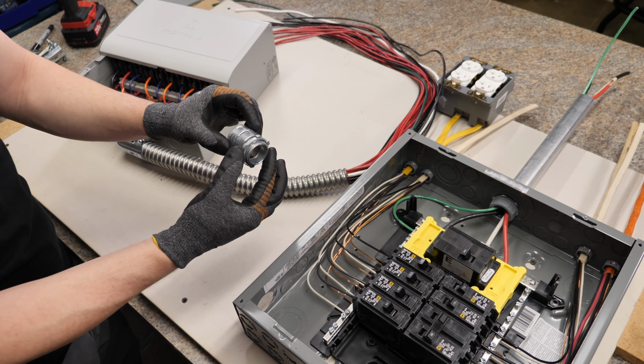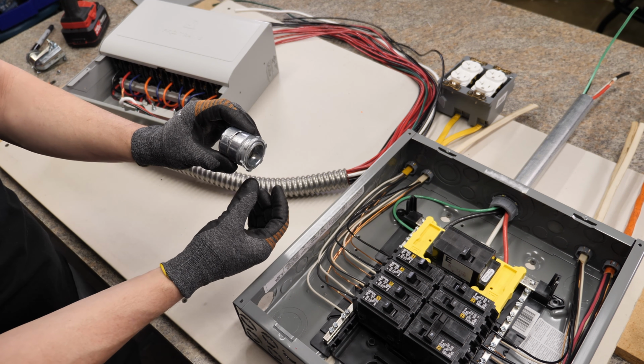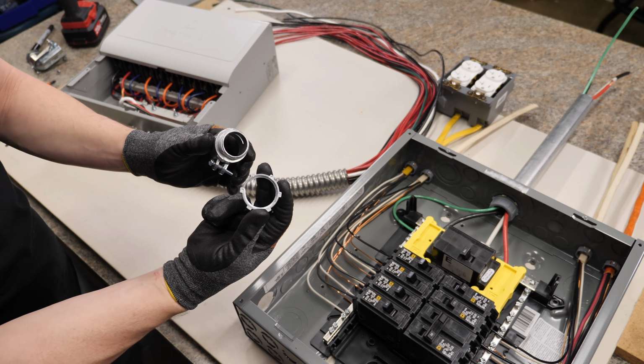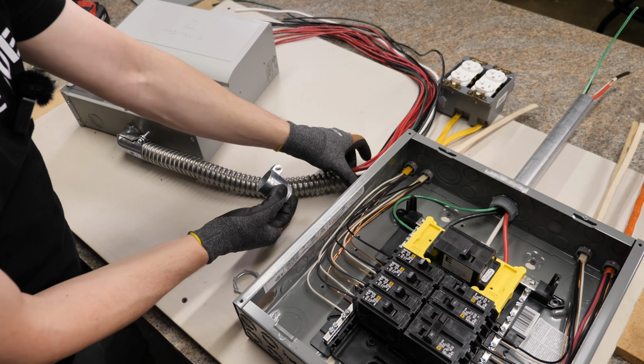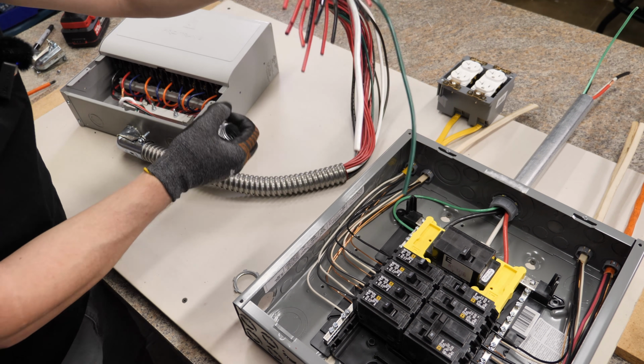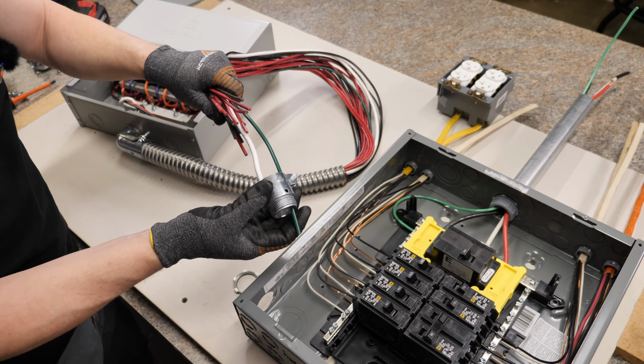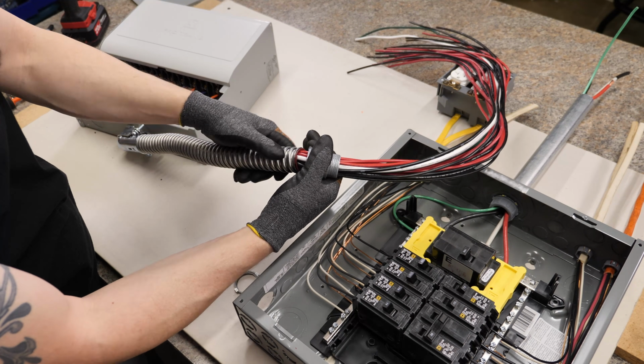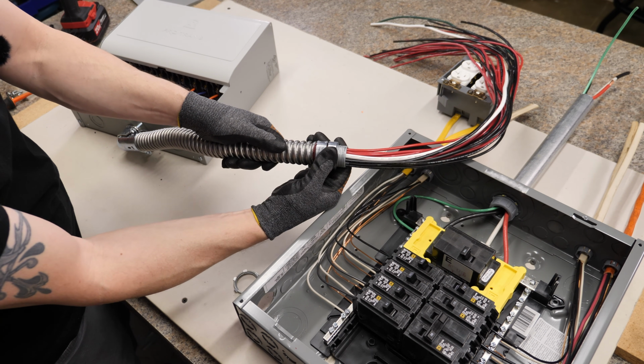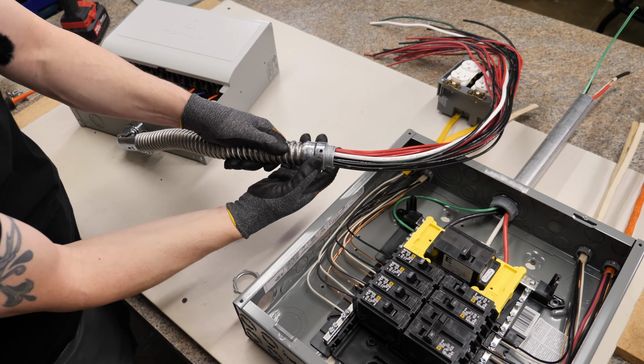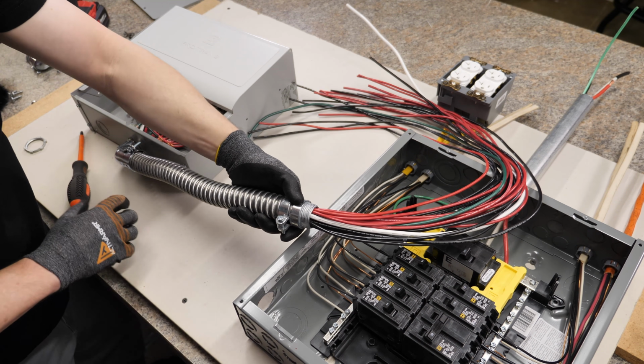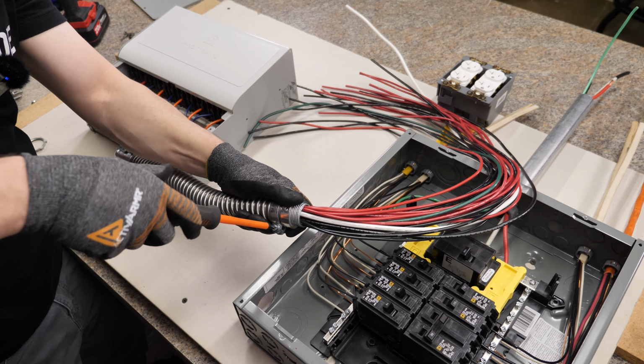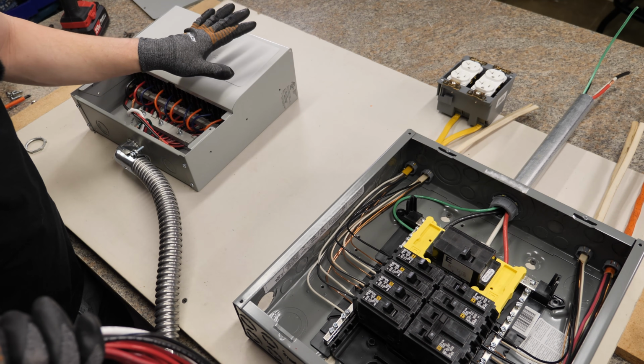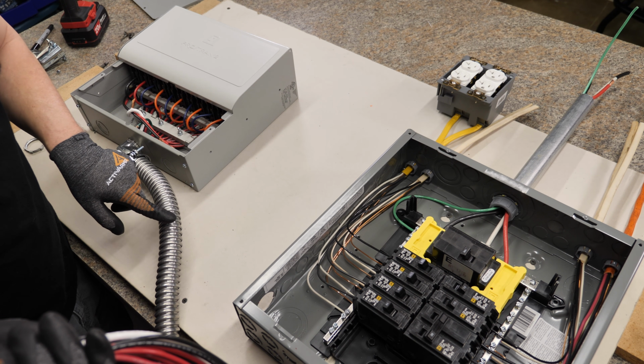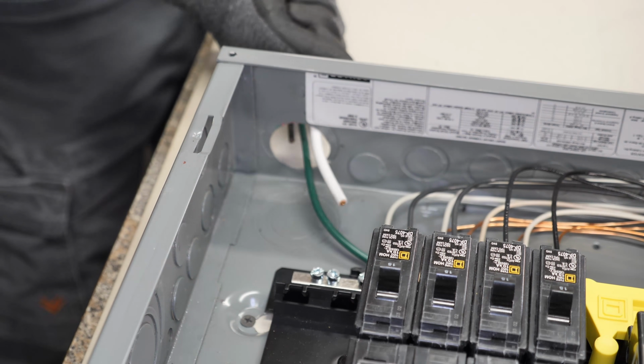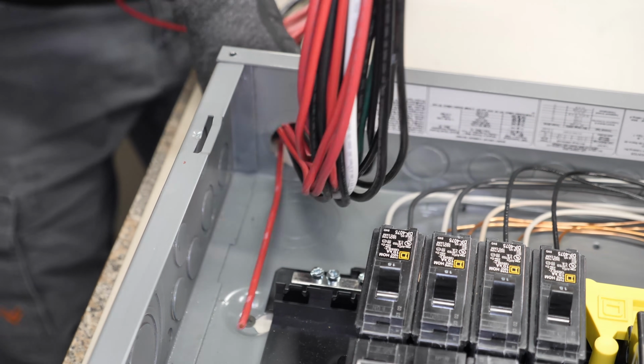We also need to use the squeeze connector that was supplied, so make sure you remove the jam nut or lock ring. Since it's easy right here, I'm going to put all of my wires through the squeeze connector first, and then we're going to put it into the main panel. Once you get down to this point, you're going to twist this into position, and once it's all the way on, you can tighten down the screw. The reason they want you to do it in this order is because if you already have this mounted to the wall, you might not be able to flex the flexible conduit and wires enough to get it into the main panel.